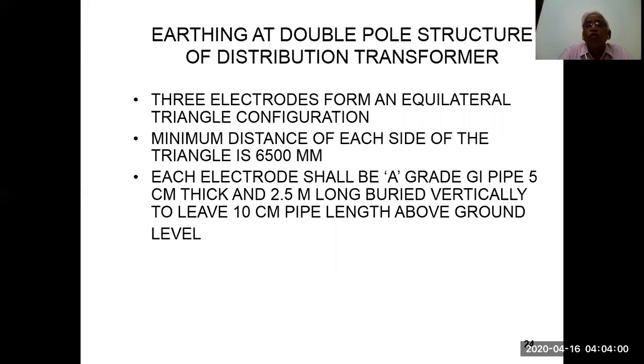Earthing at the double pole structure of the distribution transformer: three electrodes form an equilateral triangle configuration, and the minimum distance of each side of the triangle is 6500 millimeters. The earth electrode shall be a GI pipe, 5 centimeters thick and 2.5 meters long, buried vertically to leave 10 centimeters of pipe length above ground level. You can use even 3 meters, which is better. And if required, you can always use parallel pipes instead of increasing the length or diameter of the pipe.